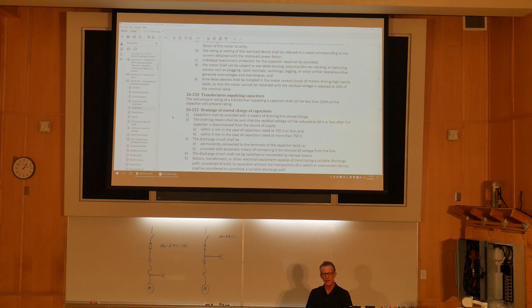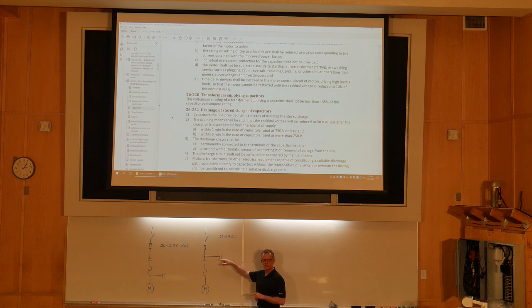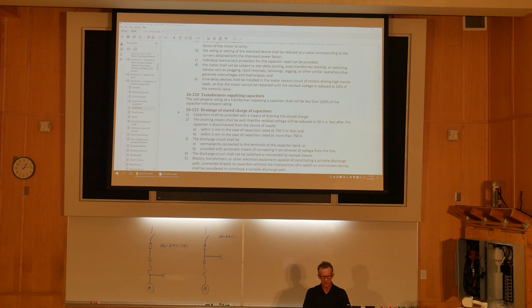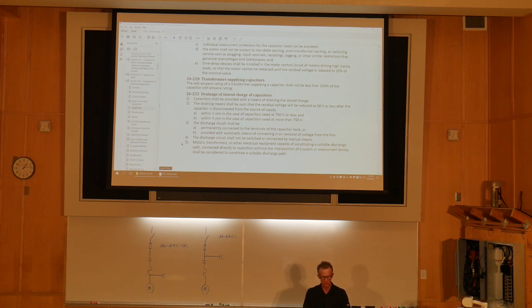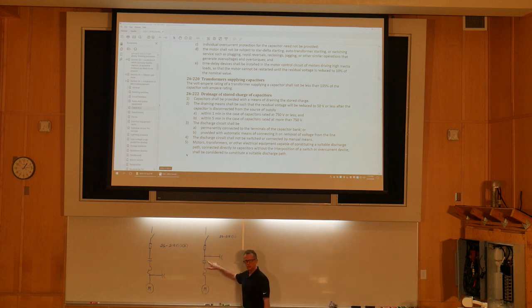Now, the drainage of stored charge, you guys. This here and this here, two different spots. This is also on the line side of the contactor. This is on the load side of the contactor. Here, I can use the motor for a suitable discharge path. It can discharge right through the motor. Here, we have to provide that discharge path. This is what I was mentioning in the earlier video. On 26222 subrule 5, motors, transformers, and other electrical equipment capable of constituting a suitable discharge path connected directly to capacitors without the interposition of a switch or overcurrent device shall be considered to constitute a suitable discharge path. That applies there. That's a switch, right? We're switching the motor on and off there with the contactor. It doesn't apply there. All right? So understand when and where.